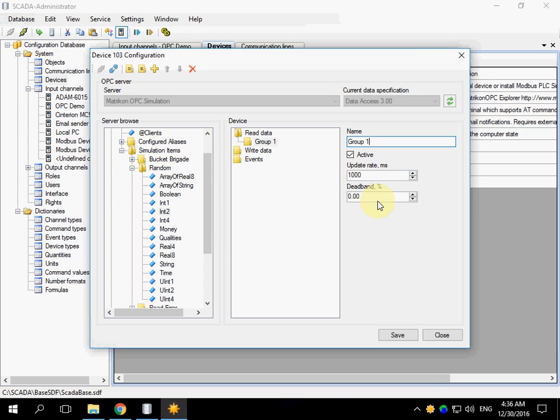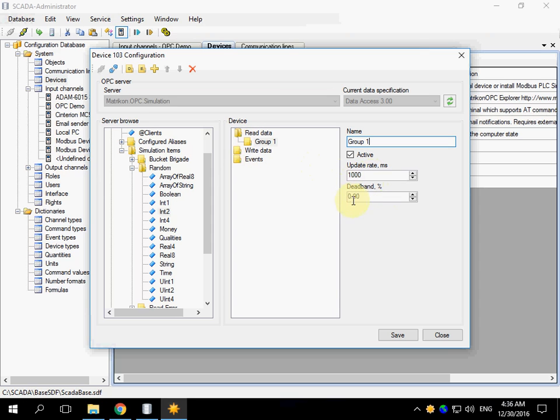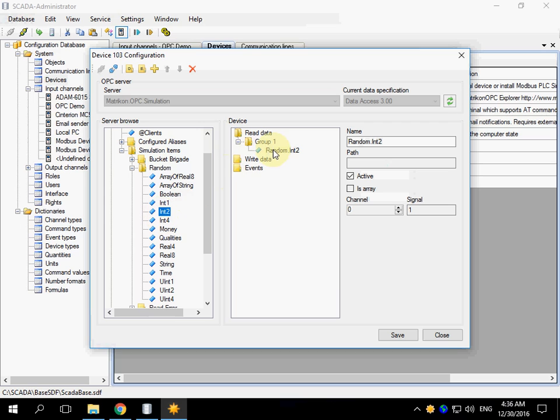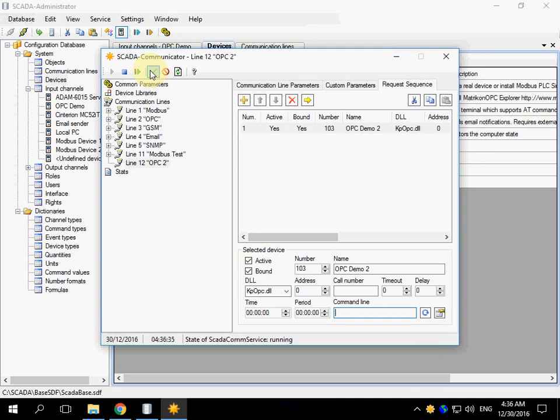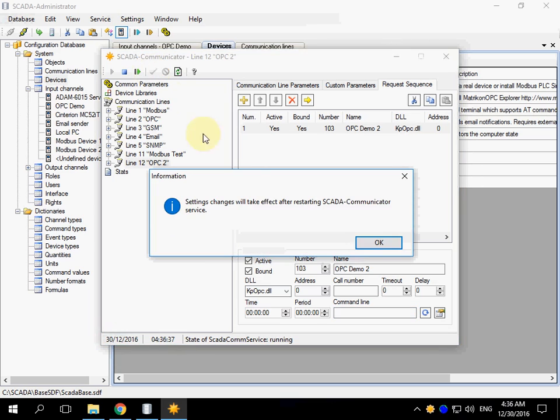These fields depend on the OPC server. You can change update rate and dead band. Double click the tag to add it to the group. Save the configuration and close the form.